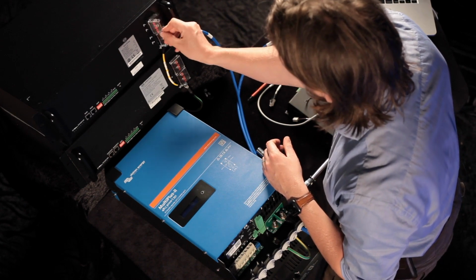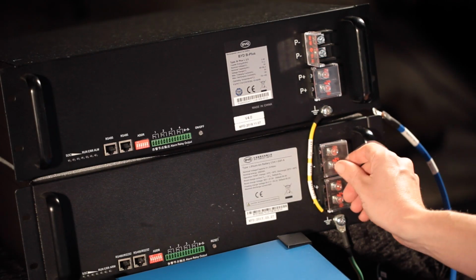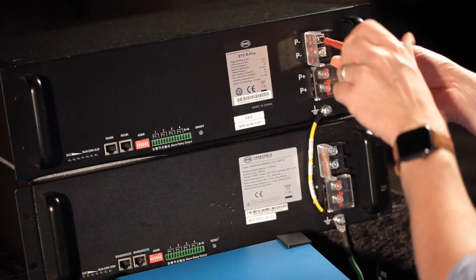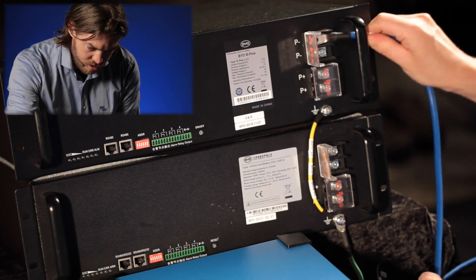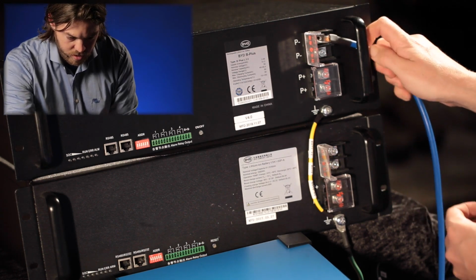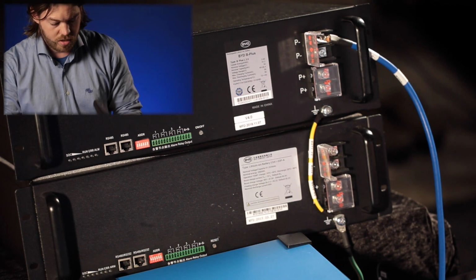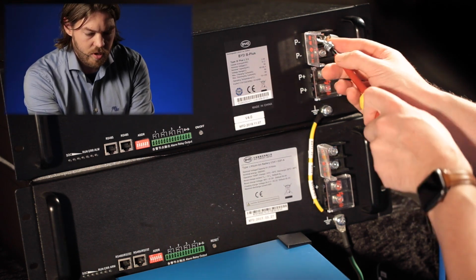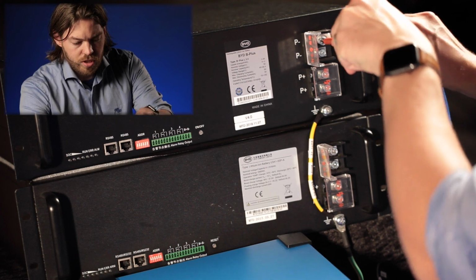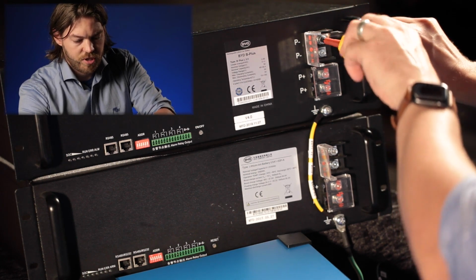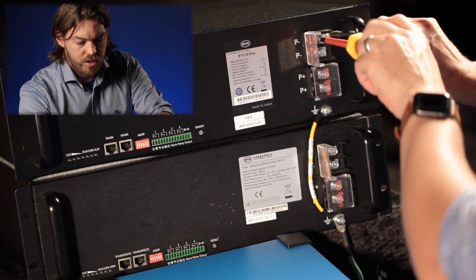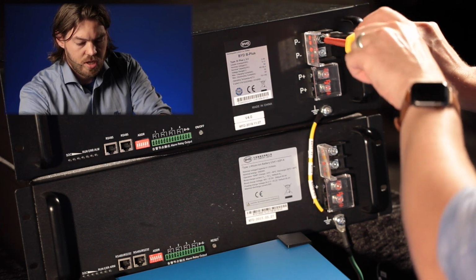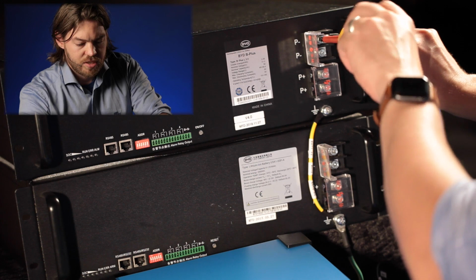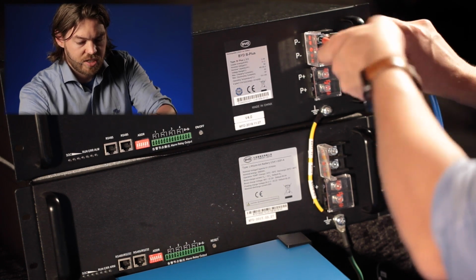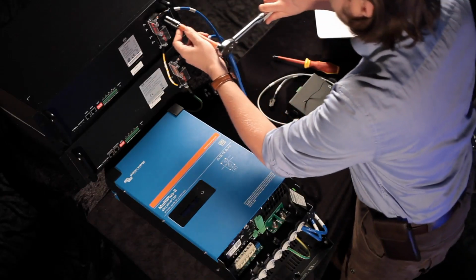Open up my P negative. There's two connections at the top. It's important to tighten these screws with the socket and not the screwdriver. I'll slide you in. It's also a good idea, just pop that in to get it started, to use the farthest connections from each other. So the outer edge points. This minimizes the potential chance of an accidental short circuit. I'll pop that in there with the torque wrench.